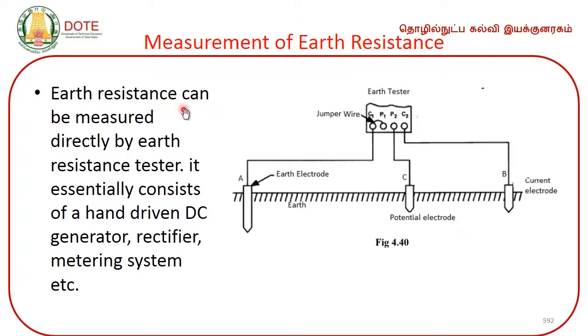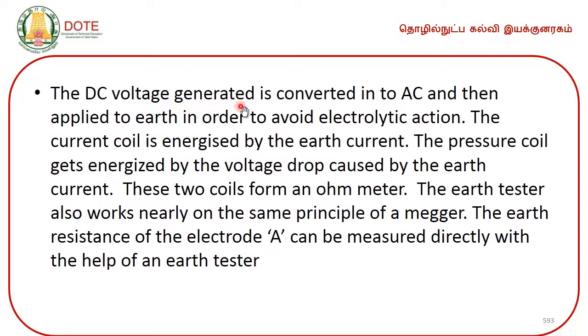Earth resistance can be measured directly by an earth resistance tester. It essentially consists of a hand driven DC generator, a rectifier, metering system, etc. The DC voltage generated is converted into AC and then applied to earth in order to avoid electrolytic action. The current coil is energized by the earth current. The pressure coil gets energized by the voltage drop caused by the earth current. These two coils form an ohmmeter. The earth tester also works nearly on the same principle as a megger.